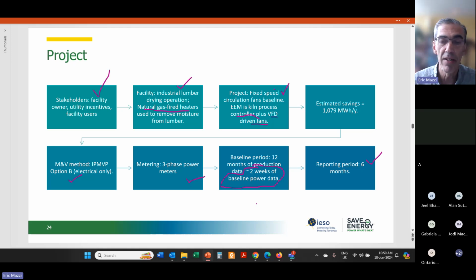We did get 2 weeks of baseline power data. The process did not vary much based on outdoor air temperature, or at least not to a degree that we could not work with that. And for similar reasons, the facility owner wanted to keep the reporting period shortened. They wanted to get the results. We had enough data, so we did not feel the need to go 12 months.